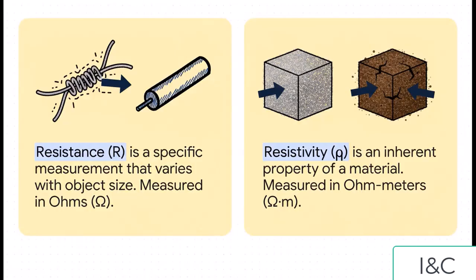We've got to pause here for a second because this is super important. We have to distinguish between two terms: resistance and resistivity. The meter gives you a reading in ohms - that's resistance. But what we actually want is resistivity, an inherent property of the soil itself. Resistance changes depending on size and shape. Resistivity is the fundamental value we're after.